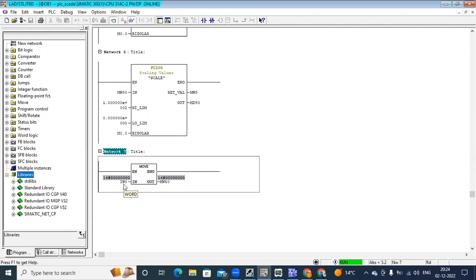There are two types of alarms. One is digital and the other is analog. Digital means on/off, like any motor trip, or an OLR trip signal that we are getting, or any digital sensor which we are sensing for some error or fault. So we are measuring digital faults. For analog, it will be like limits. We are setting limits, like if it is crossing some value, we should get a message.